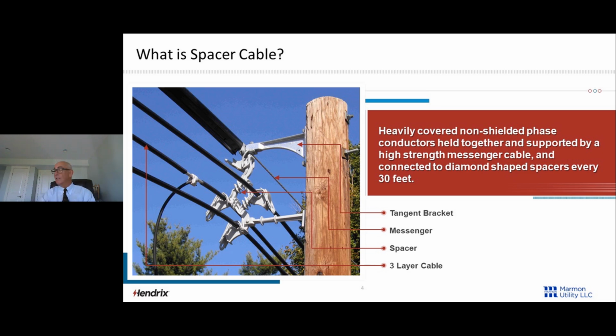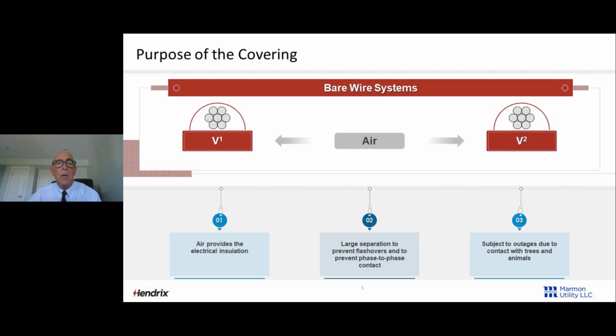Then we got a couple of brackets: tangent bracket, angle bracket, dead end bracket. Very simple system. So why do we need the covering? We'll talk a couple of theory slides. When we use a bare wire system, we're basically using air as the insulator. Air is a halfway decent insulator, but you need a whole bunch of it in order to get a sufficient BIL on a 60 hertz withstand.